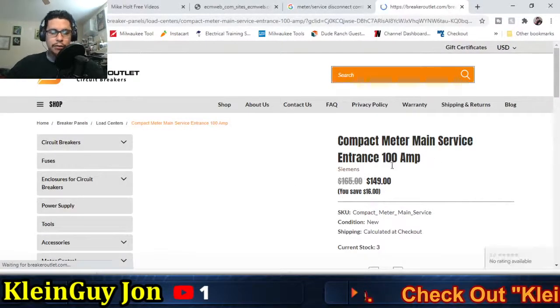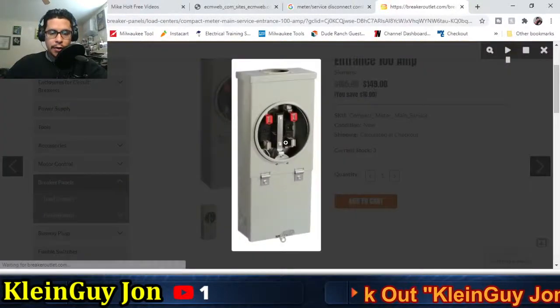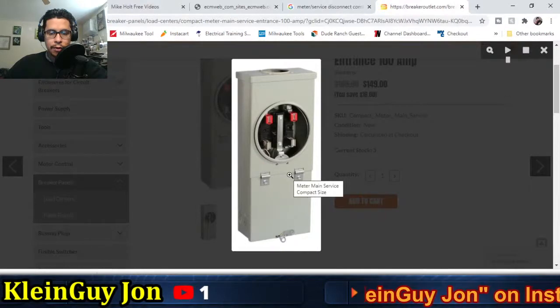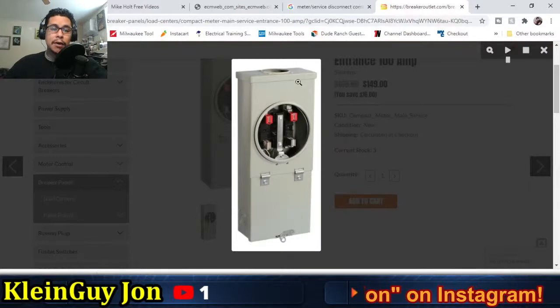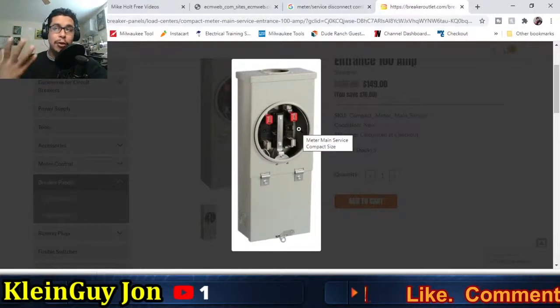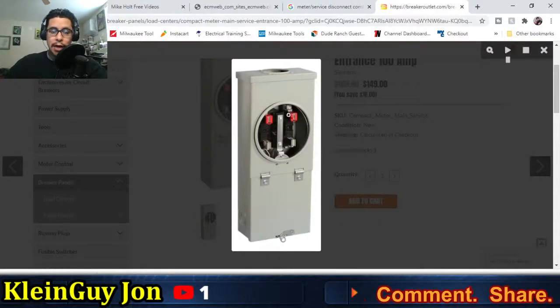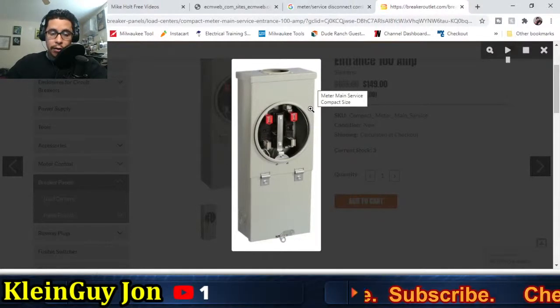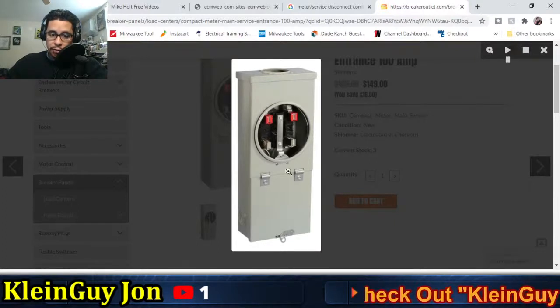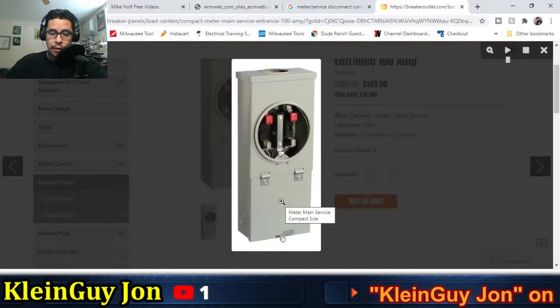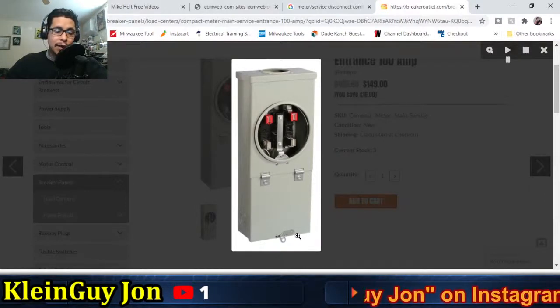So this is what they call a compact meter main service entrance, 100 amps rated. I would think, the way I look at it, this compact meter main service, the entire thing will be considered a service. You have a meter on the top, you have your disconnect in the bottom. This would have to maybe be considered a service, or they would still consider not the meter, not the service, even though it's in the same enclosure, but the disconnect as a service. But to me, what I see, as far as I'm concerned, I would have to see this as a service.